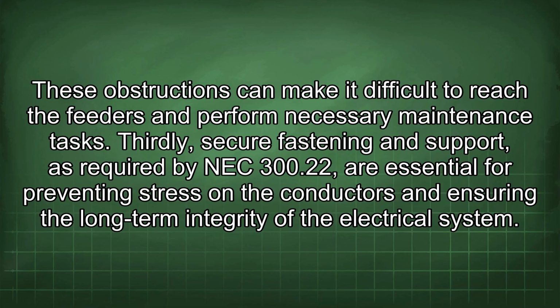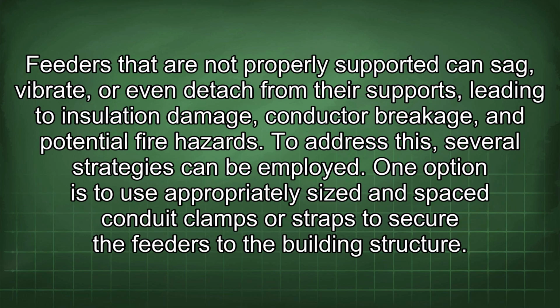Thirdly, secure fastening and support, as required by NEC 300.22, are essential for preventing stress on the conductors and ensuring the long-term integrity of the electrical system. Feeders that are not properly supported can sag, vibrate, or even detach from their supports, leading to insulation damage, conductor breakage, and potential fire hazards.